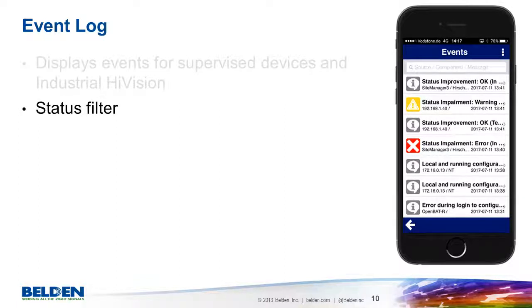As there can be a lot of events in the list, we've added an event filter. It's possible to view just warnings and errors, just unacknowledged warnings and errors, or all unacknowledged events. To get even more specific information, there's a search field. It's possible to search on event source, component, or message. So, for example, typing in an IP address will display all events for that device only.